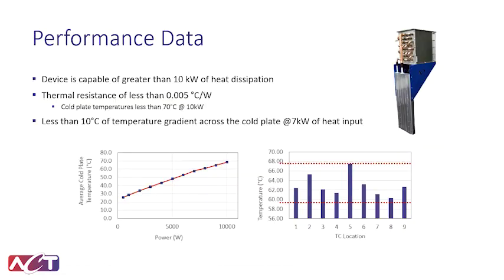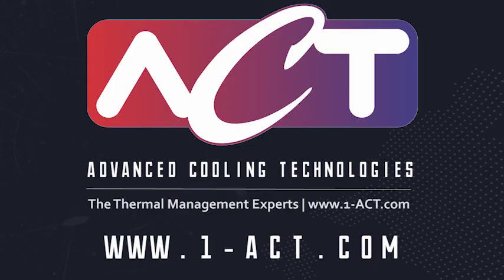Finally, there's performance data shown here. This is for a typical power electronics application where we're dissipating up to 10 kilowatts of heat. We're showing data for 7 kilowatts on the right. You can see that the two-phase nature of the cold plate allows your temperature gradients to be reduced. You can maintain all of your modules mounted on one cold plate within 5 to 7 degrees C even at up to 10 kilowatts of heat. For more information you can find it on our website at www.one-act.com.